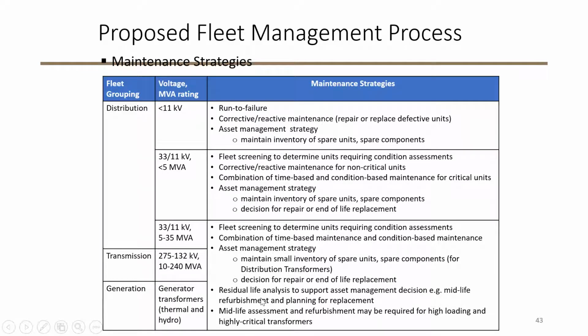For larger transformers, you should do residual life assessment and midlife assessment before midlife refurbishment, then decide criticality of components and do optimized maintenance. That means you shouldn't replace bushings one time, do oil filtration the second time, OLTC maintenance the third time, and oil replacement the fourth time—know the major problems after midlife and resolve everything in one go, in a planned, phased manner, to extend the life of the transformer.